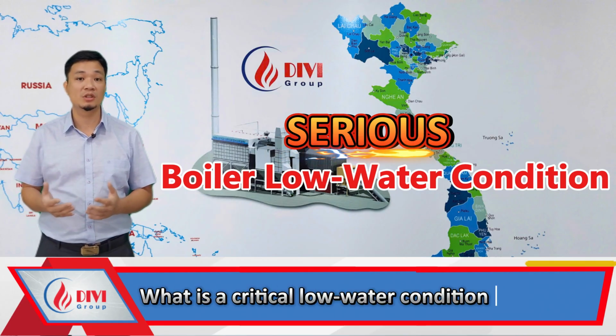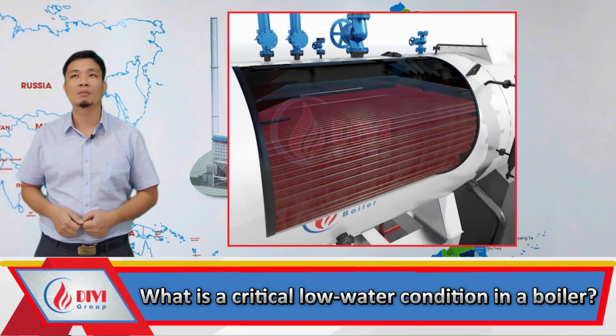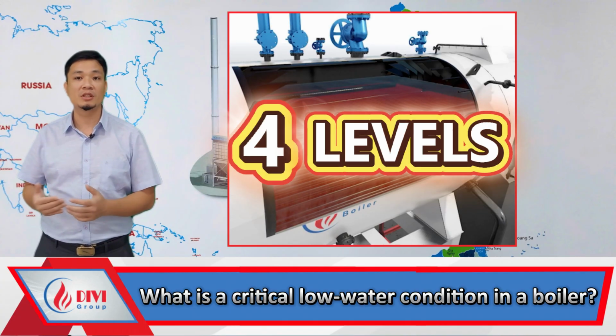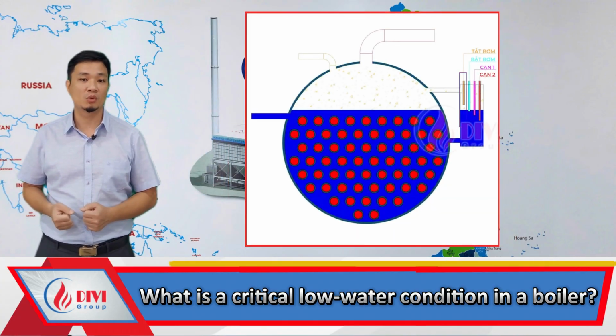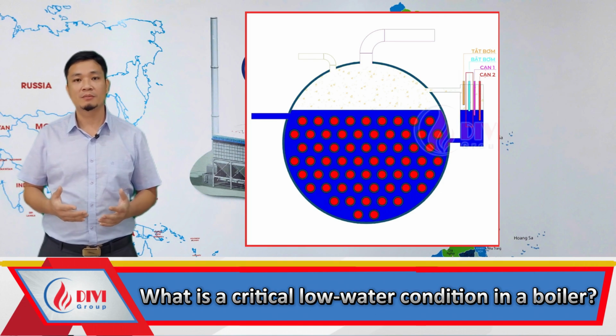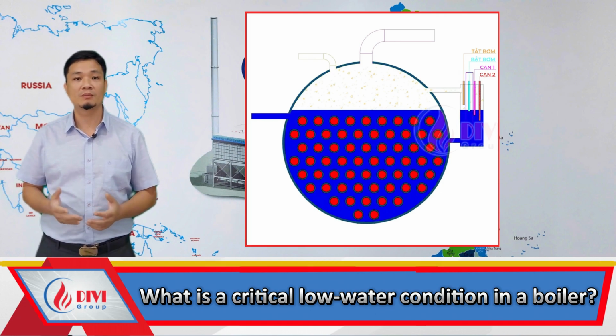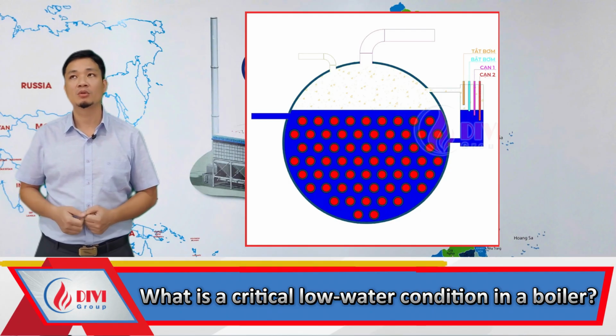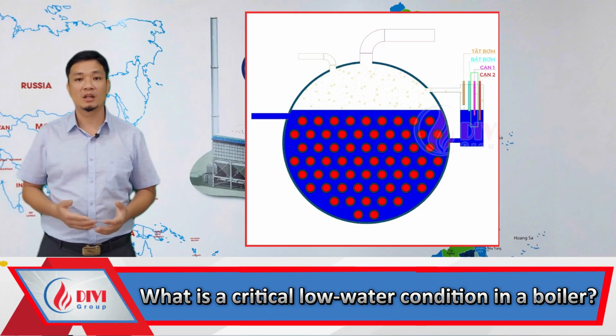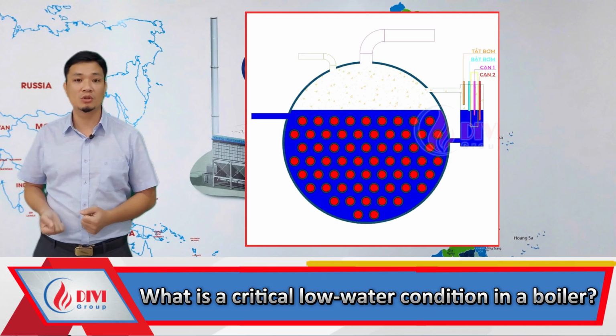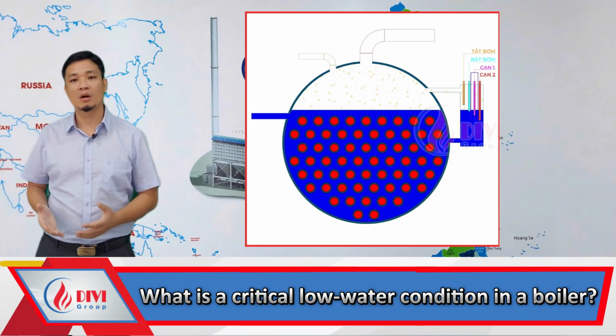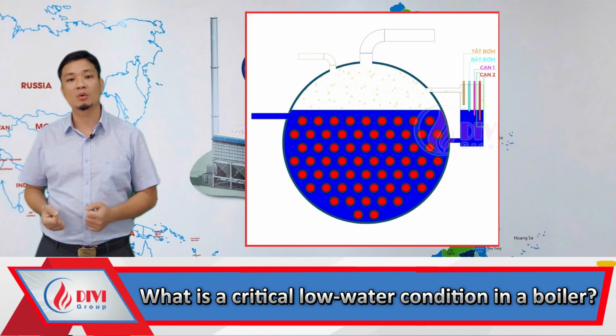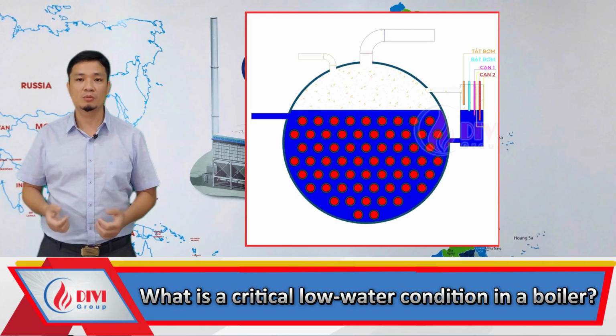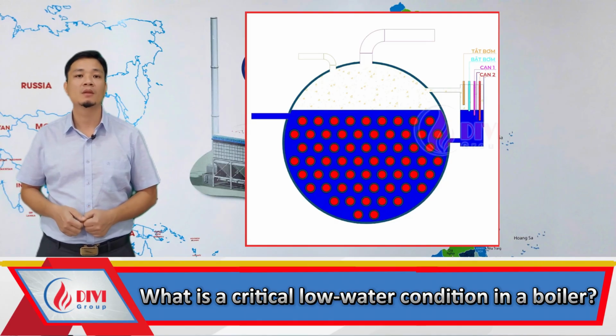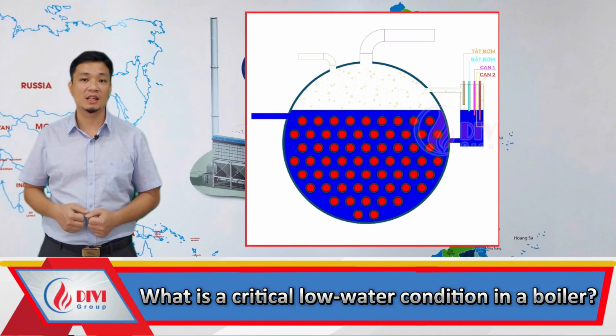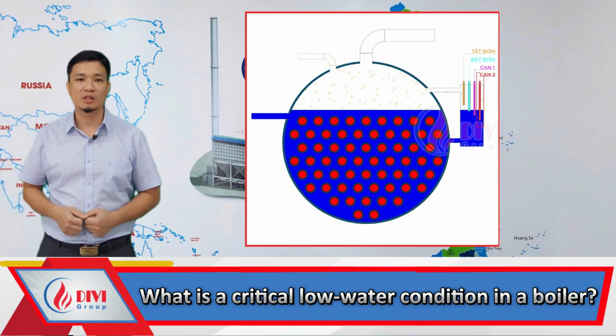What is a boiler dryout condition? As you may already know, boiler water levels are categorized into 4 basic stages. Level 1, full water level, feed water pump stops. Level 2, low water level, feed water pump starts. Level 3, low water alarm, warning level 1. Visual and audible alarms are triggered. Boiler continues running in automatic mode. Level 4, critical low water alarm, warning level 2. Emergency alarms activate. Boiler locks out automatic mode and can only be operated manually or with a supervisor's password.